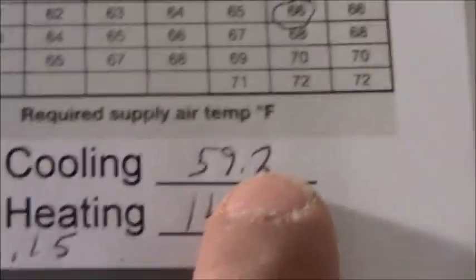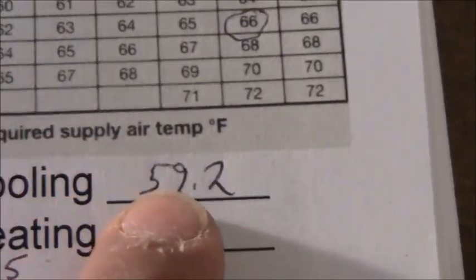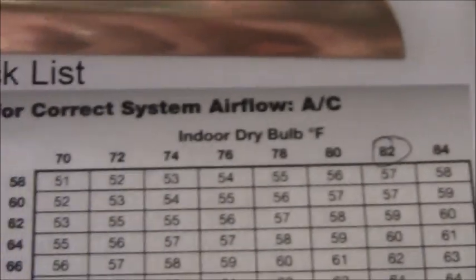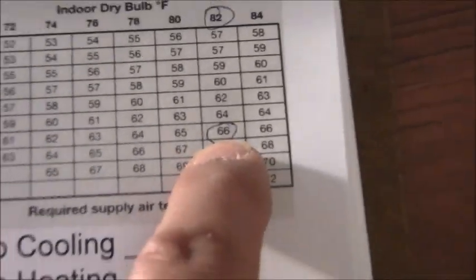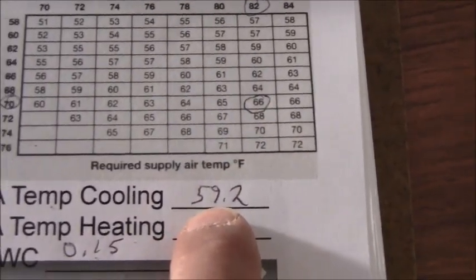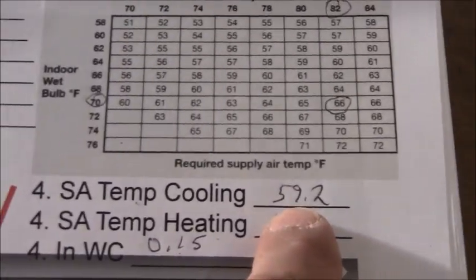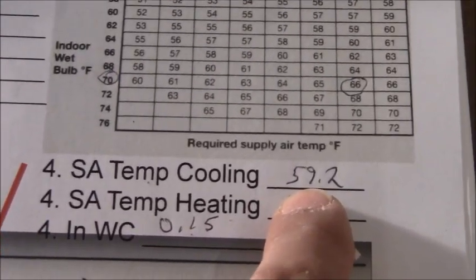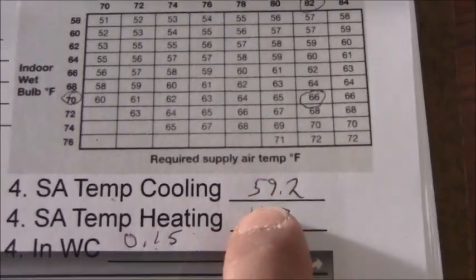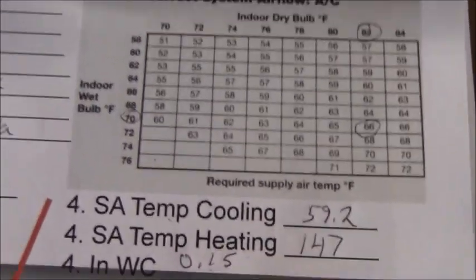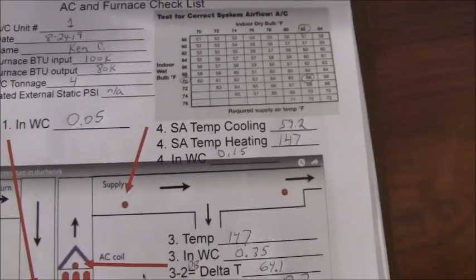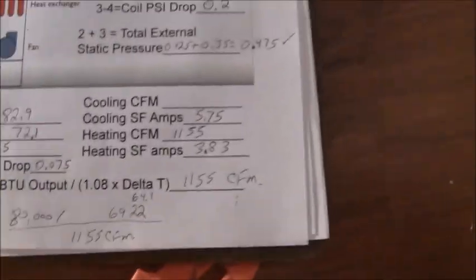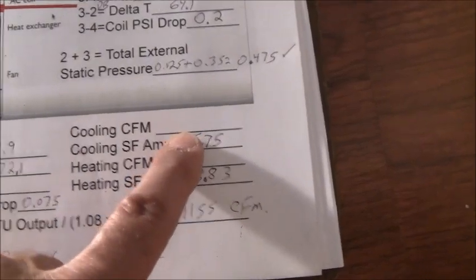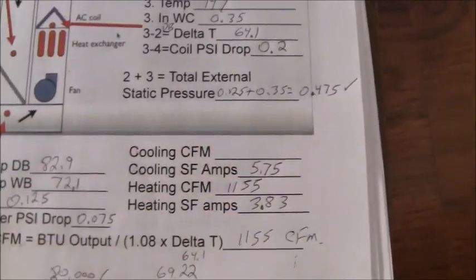I'm actually getting 59.2. So if I'm getting a lower temperature than what the chart is telling me, it's possible that there's too much residence time of air, so the fan could be spinning too slowly. This fan could be increased, but that's not bad. And that is that. I can't tell you the cooling CFM. I need an anemometer, and I don't have an anemometer. I wish I did, but I gotta blow the 80 bucks and buy one.